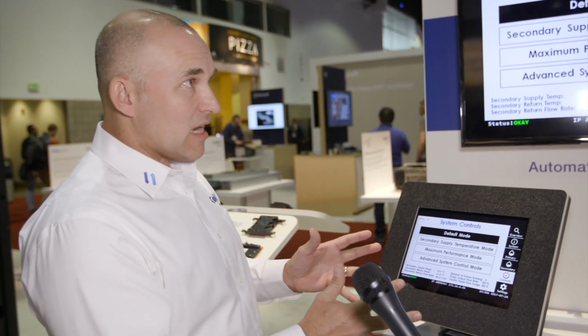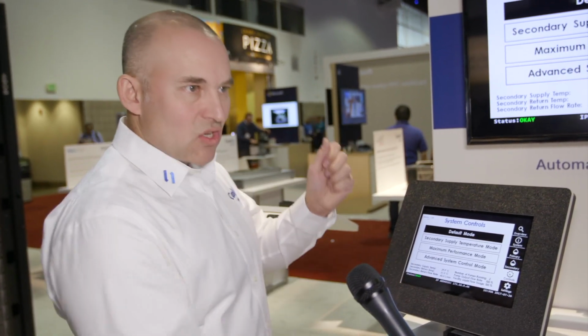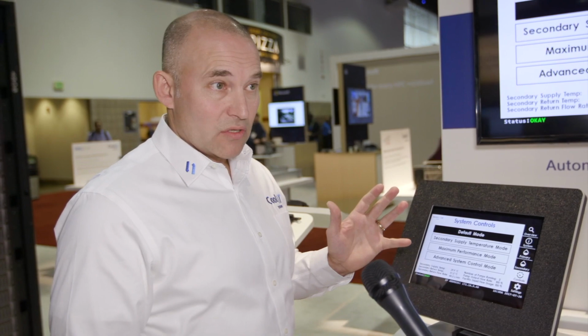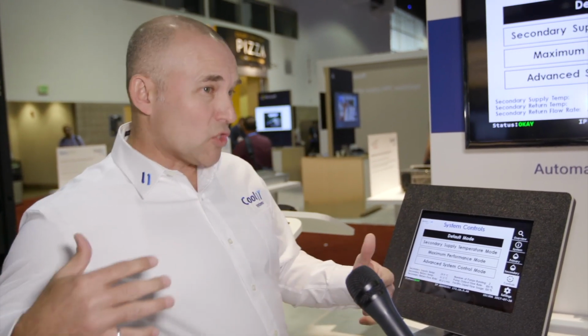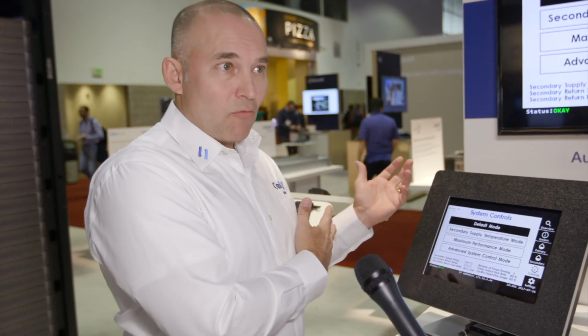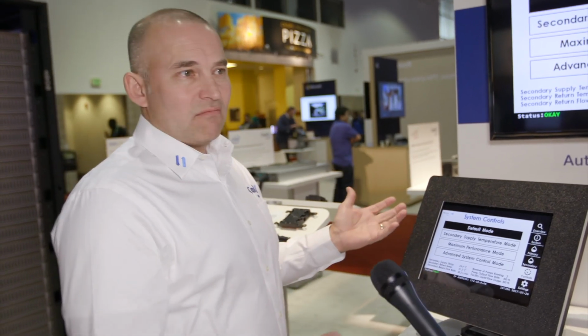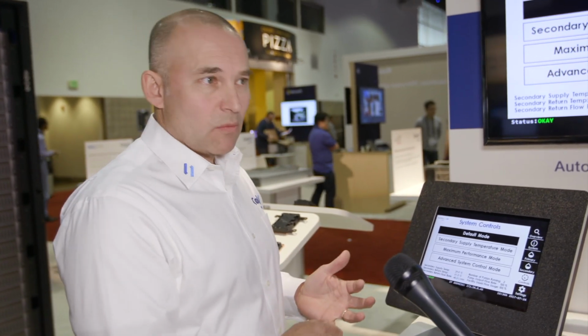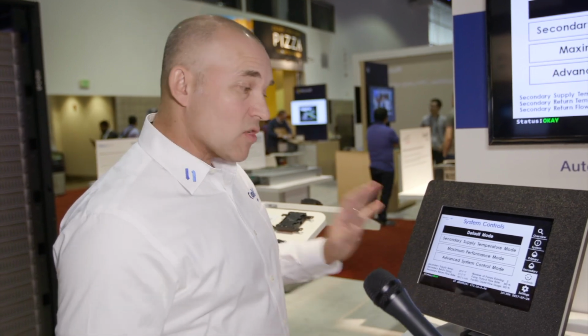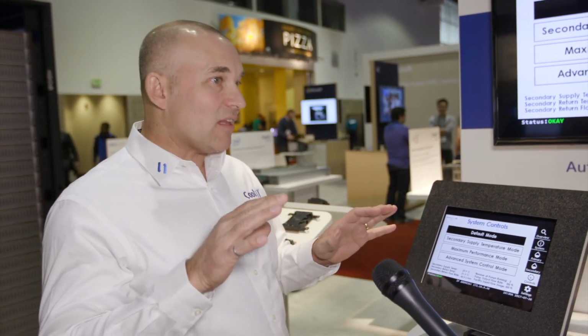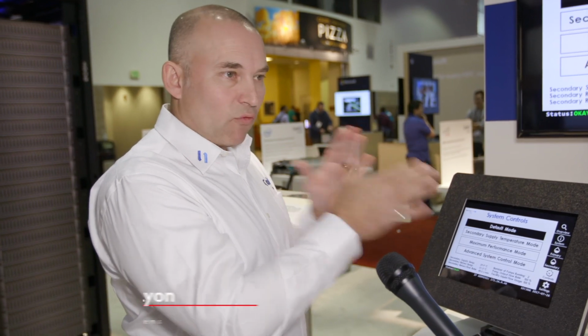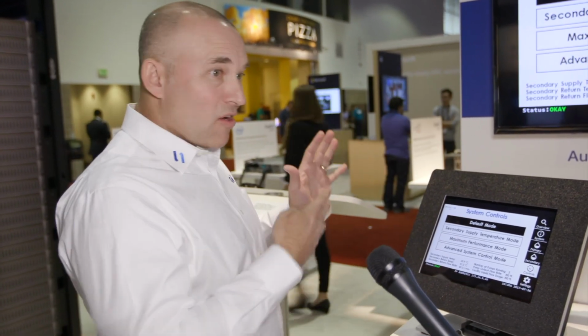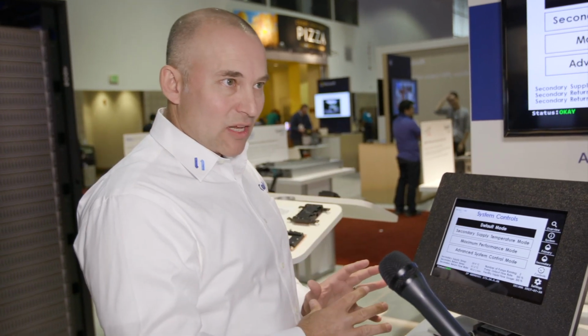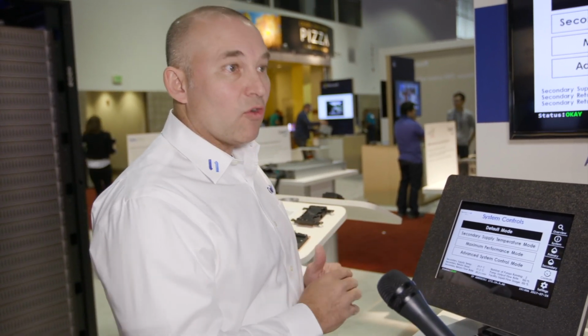So as an example, if we didn't have that and the pumps are going 100%, and I then disconnect all the servers on one of the manifolds, well then it's going to be trying to push twice as much flow through the remaining connections, which isn't necessary. It takes up way too much power. It's actually hard on the pumps. So what this does is it monitors exactly how much differential pressure there is, so that it'll notice that there's less space for the water to go and lower the pump capacity so that it keeps only the appropriate amount of flow no matter what you do.